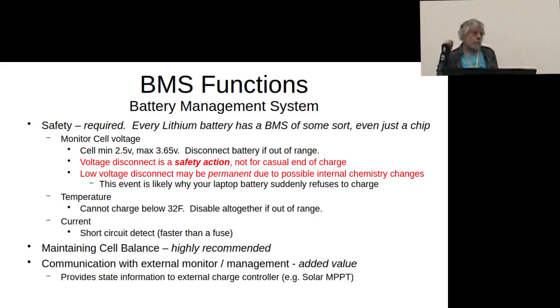Safety is what it says - it's not to protect the longevity of the battery so much, it's to keep it from blowing up. If you go above 3.45 volts per cell, 3.65 volts per cell, bad things happen to the lithium iron phosphate battery. Below about 2.5 volts, 2.2, 2.3, somewhere down in there, there's a chemical change that happens inside the cell that grows little dendrites and things that can short the battery out.